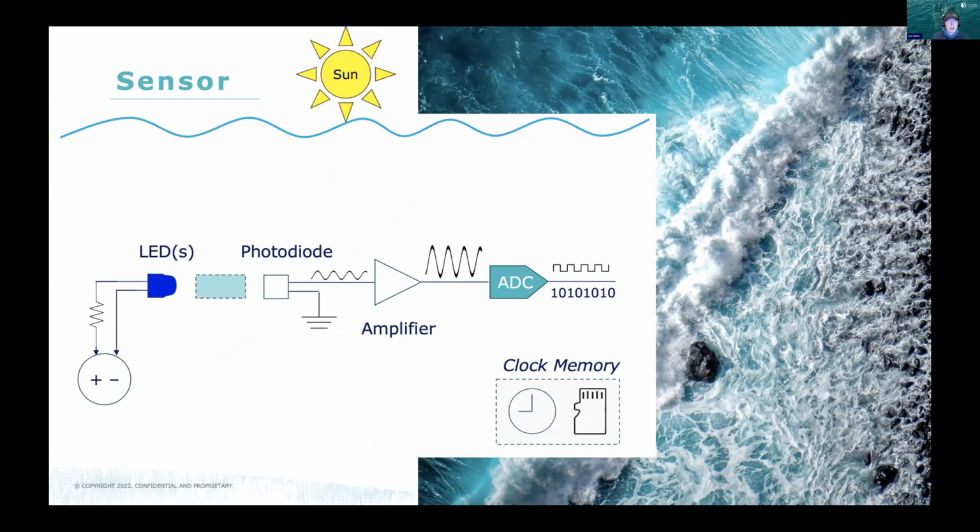So there's an amplifier and other signal processing to make this signal bigger. Then it goes through what's called an ADC, an analog to digital converter, where it's converted into digital numbers. That's what you see on the output ultimately, usually in some ASCII and in some instruments binary format. Optionally, our sensors may have a clock and some memory. The ones we're looking at today, I won't focus on that part. We'll assume that the platform itself provides time and other aspects of it.